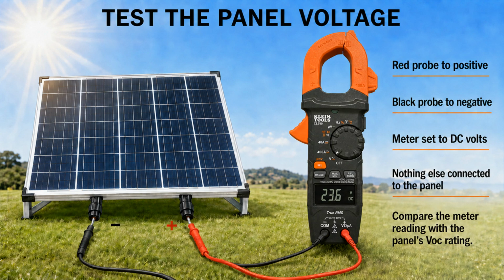Plug the black lead into COM and the red lead into the voltage and ohms port. Turn the CL390 to the voltage position and select DC voltage. Touch the red probe to the panel's positive connector and the black probe to the negative connector. Compare the meter reading with the VOC rating on the label. Our example label says 24.3 volts, and the meter shows 23.6 volts DC. The panel is producing voltage.